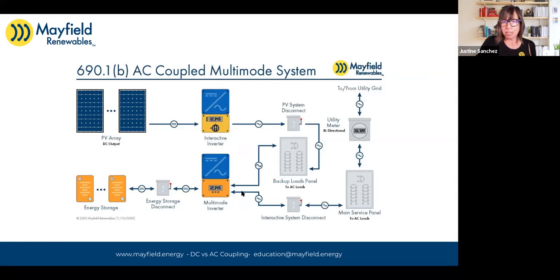So this line is basically open. There's a device inside this multi-mode inverter—we can call it a microgrid interconnect device, a new term the NEC put in, maybe around 2017. That device is in charge of making sure it's not pushing any PV or energy storage power back onto the utility lines during an outage situation.